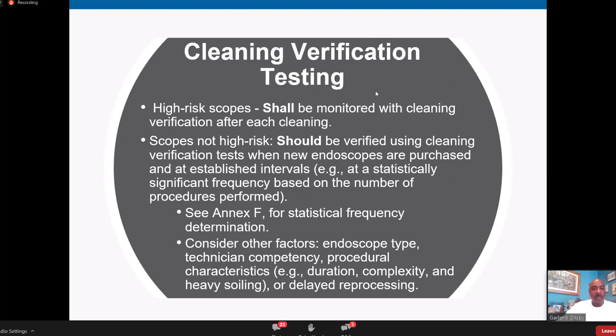And that's a question I have here. Is ATP an option? Yes, it is an option, one of the many, and this would be where it's used after manual cleaning. So I think that takes care of most of the cleaning verification. Asking for examples, we did that. Ways to monitor, we talked about that. So follow the instructions from whatever cleaning verification test you're using, making sure we're doing it at this point in the process to show that you've achieved that cleaning level. Sometimes we see them used after disinfection, and that's not appropriate. No cleaning verification test is meant to be done at that point. It's on a scope that's been cleaned, but not yet terminally sterilized or disinfected. Sorry for that interruption, but I was realizing that people didn't know what we were talking about. Thank you. Next.